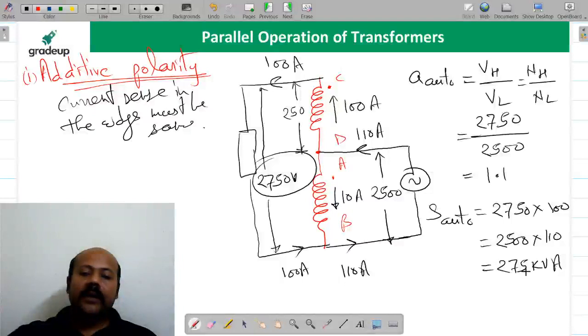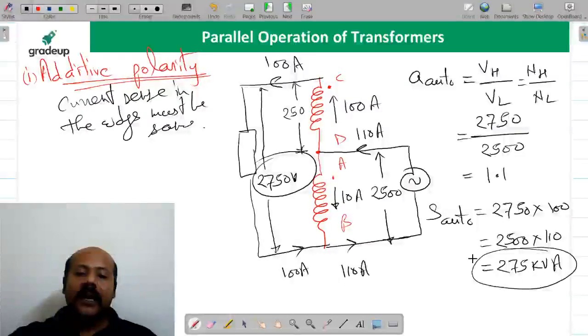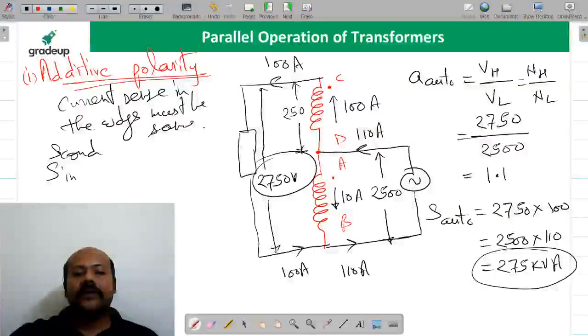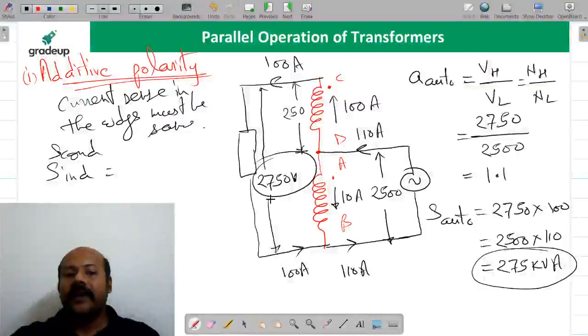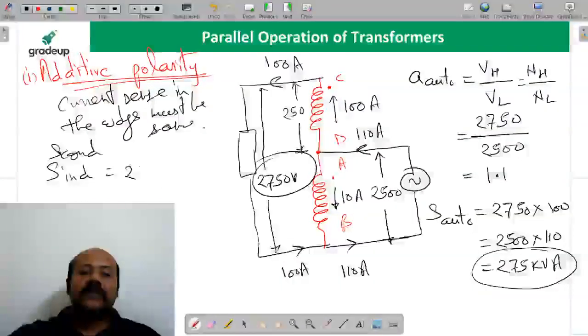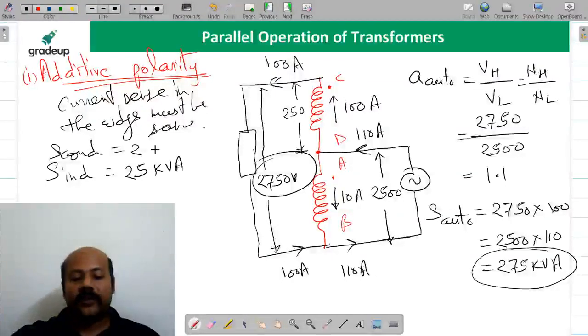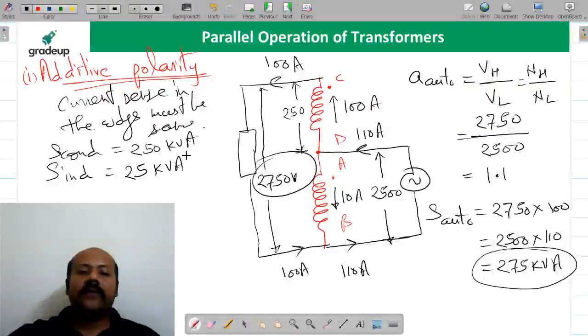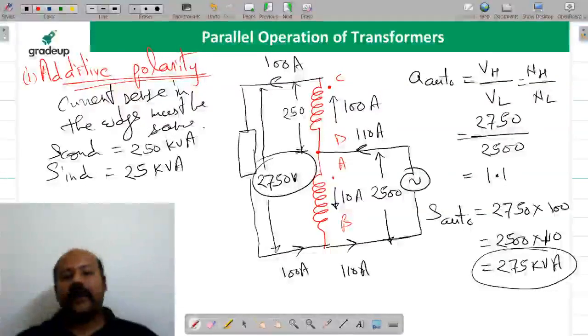Now you see, this is the total kVA of the auto transformer. Can you tell me what is the conductively transformed VA and what is the inductively transformed VA? When this transformer was used as a two-winding transformer, the kVA rating was 25 kVA. So inductively transformed VA is 25 kVA, and the rest is the conductively transformed kVA, so that the total is 275 kVA. I hope it is clear to all of you.